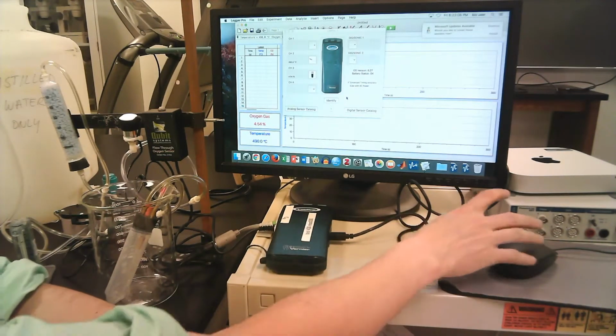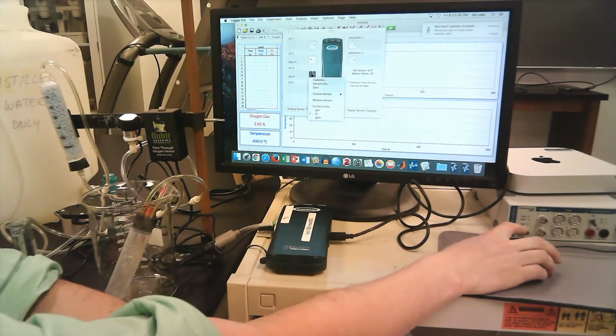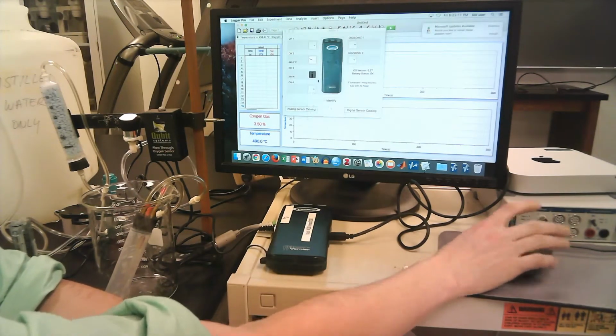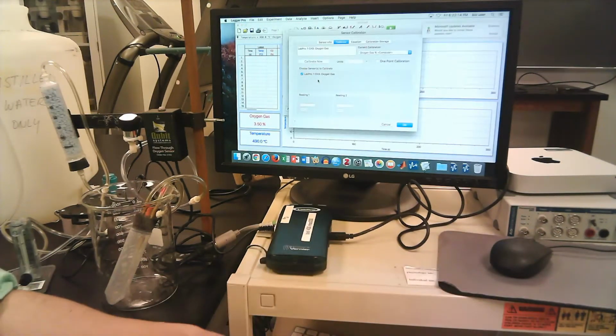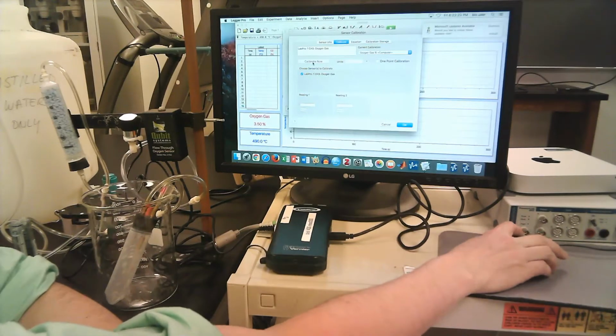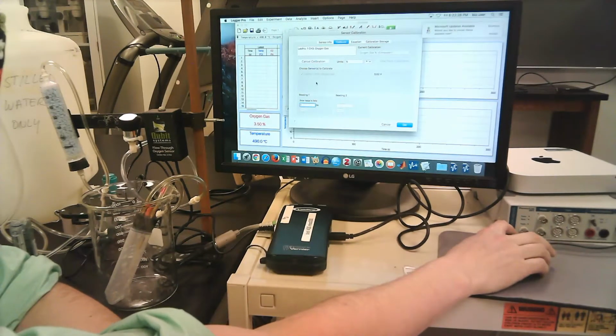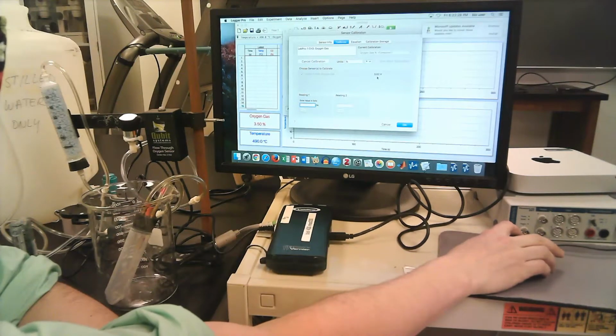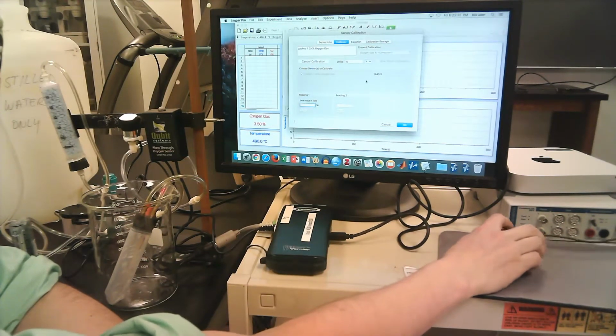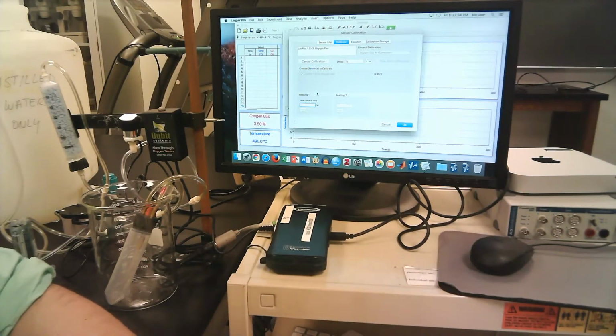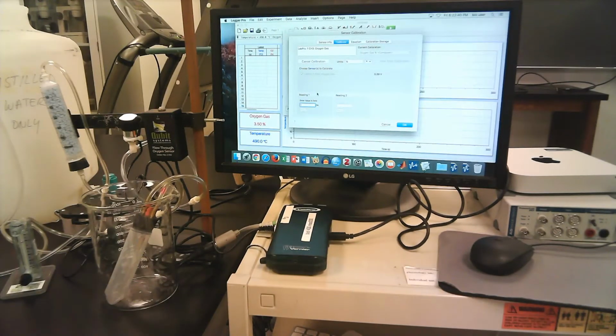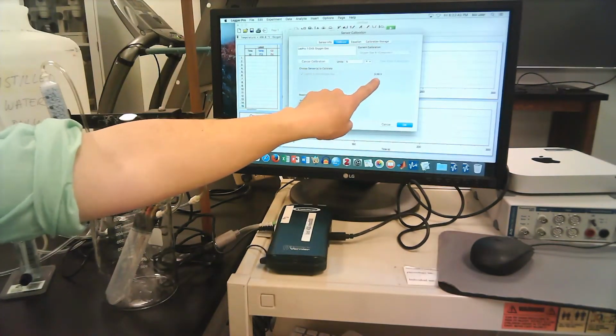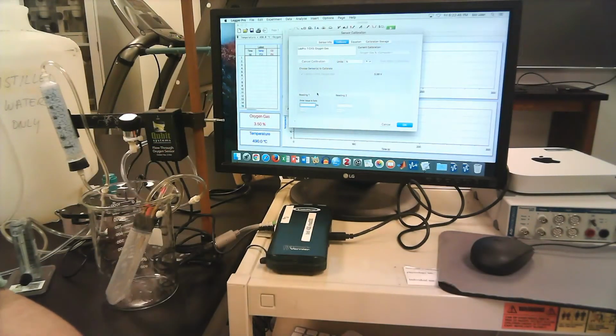Okay, so now if I want to calibrate, I can just click this oxygen sensor icon, and there's a little calibrate menu up top. And that's going to open up a dialog that looks like this. And what we're going to do is press the Calibrate Now button. And we're going to let this run for a little while. So it's giving me a voltage reading. And generally you want to wait for about 2 minutes until the voltage reading starts to stabilize, right? So right now it's slowly going down. It's gone down to 0.39 volts, 0.38.